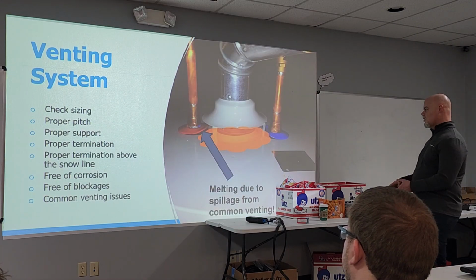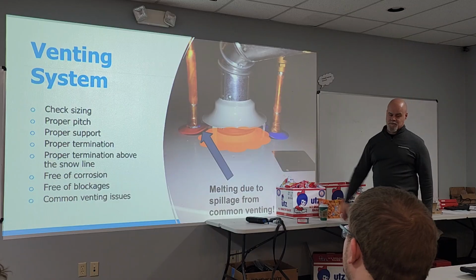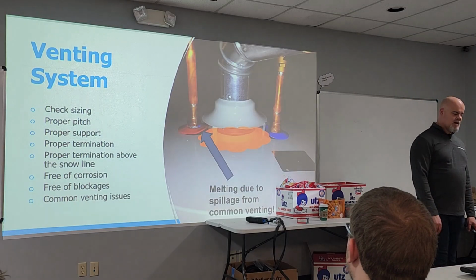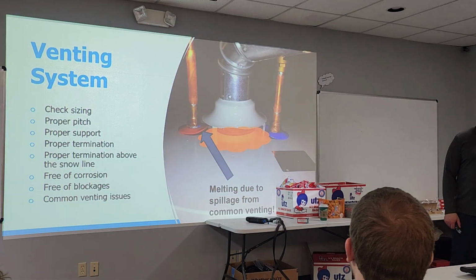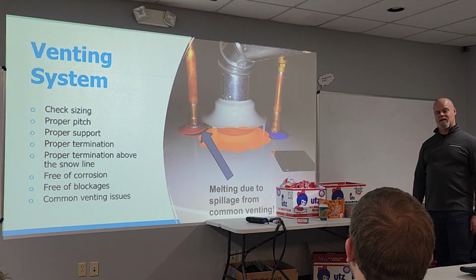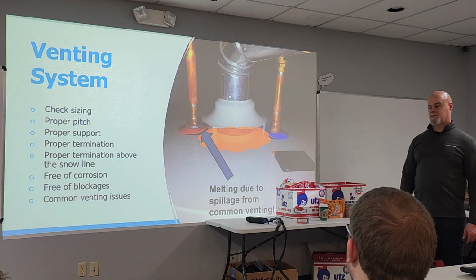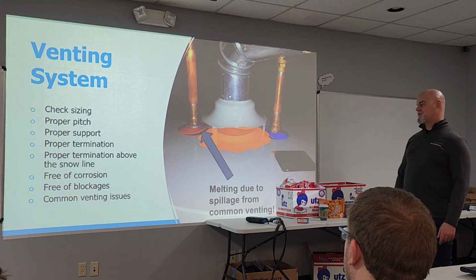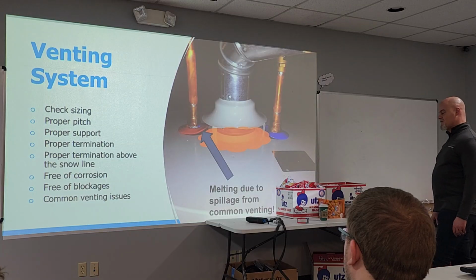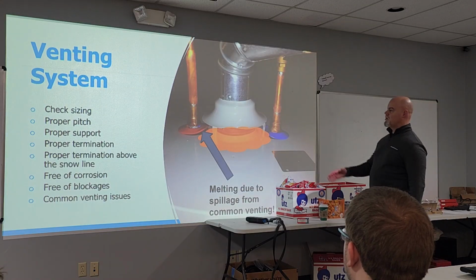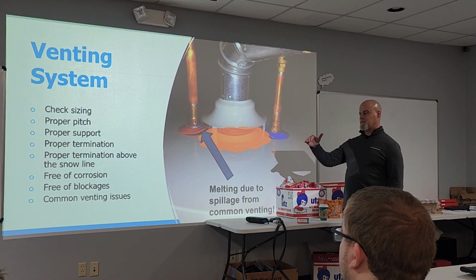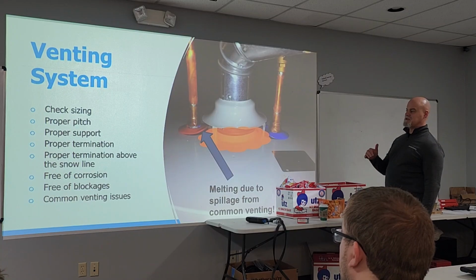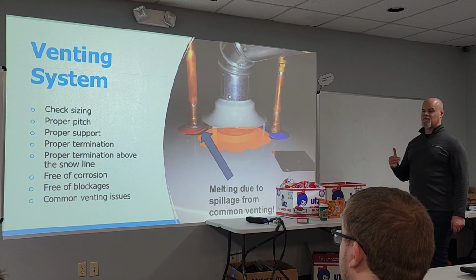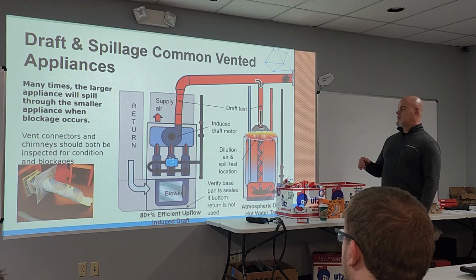Ever see this before? Spillage. By the way, flue gases and CO, carbon monoxide, don't leak, they spill. That's another thing learned from the National Comfort Institute, very important. Never leaks, always spills. So we need to check sizing, pitch, proper support, proper termination above the snow line, free of corrosion, free of blockages.